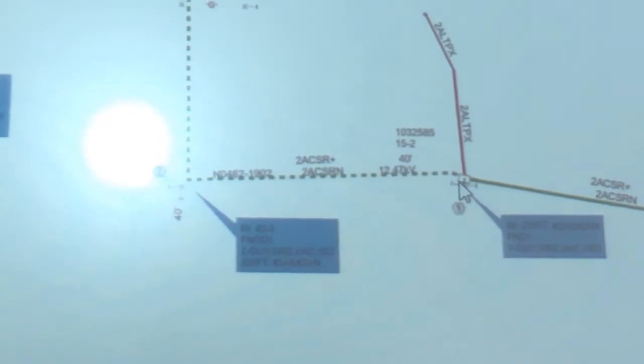So, in recapping, remember, solid line is already installed. Pole here, installed transformer, same thing here with the pole and transformer, and green is conductor, red is secondary. So those are services. Come here on the job print, the new business part of this job, which you'll be building, all dotted lines for wire installation. Green is conductor, primary and neutral. Red dotted is installed service. The asterisk here is indicating service pole for the customer.